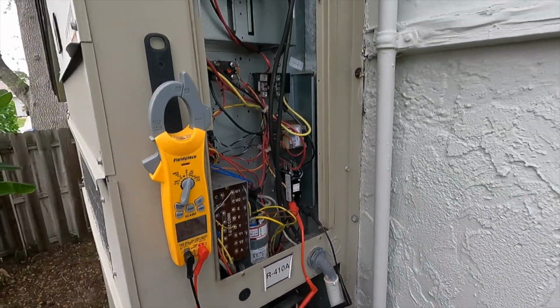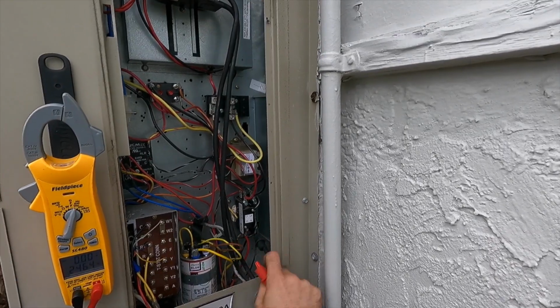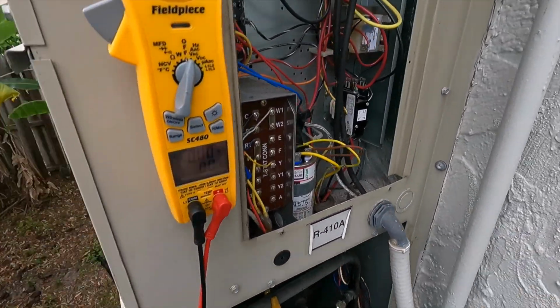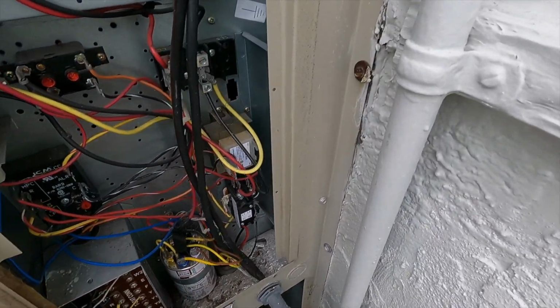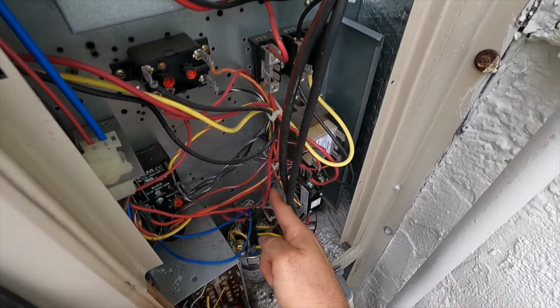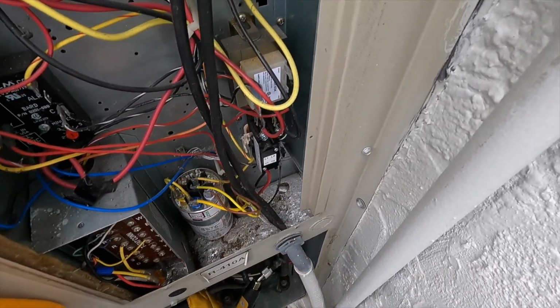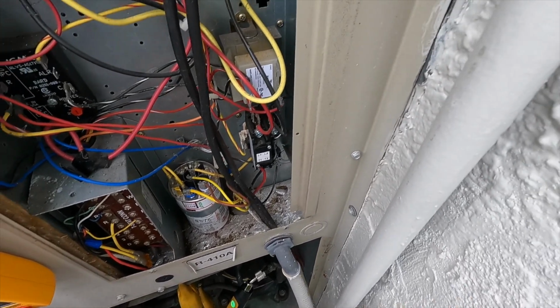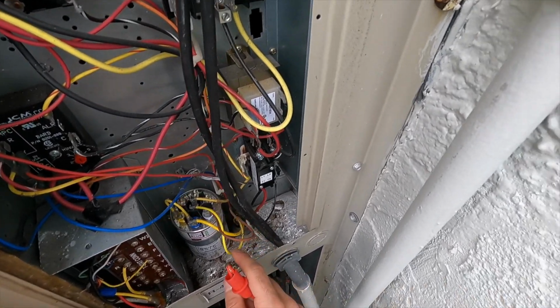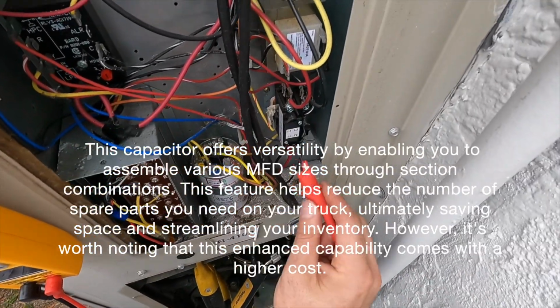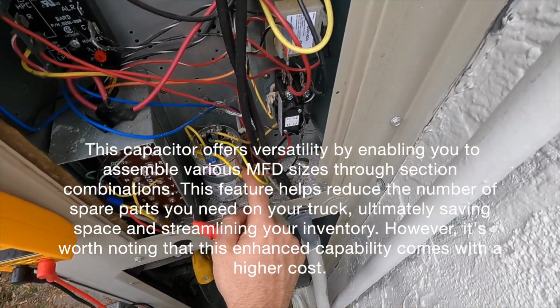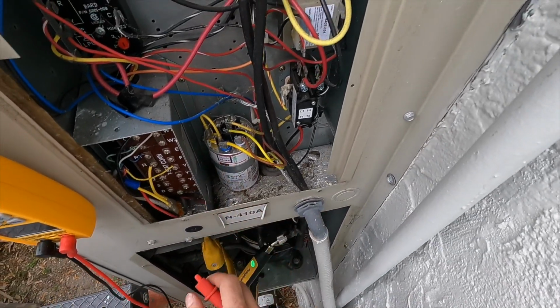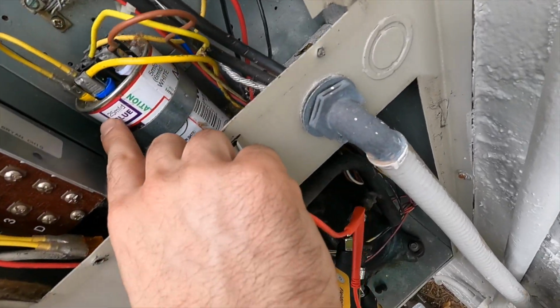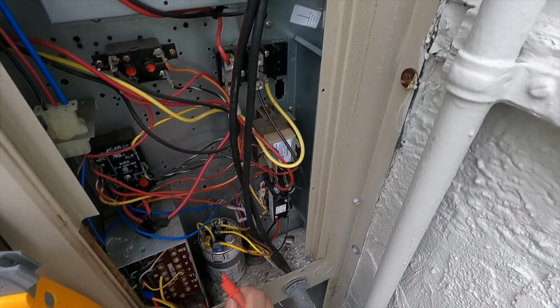All right, so I'm going to show you now how we're going to take an under load microfarad check. So this one's going to be a little more difficult, only because it's a different kind of capacitor. All right, so our middle is going to be our common from the single pole contactor. Our yellow here should be our compressor. Our brown should be our fan. So 25 microfarads plus 5, so we got 30 total microfarads is what we're looking for.